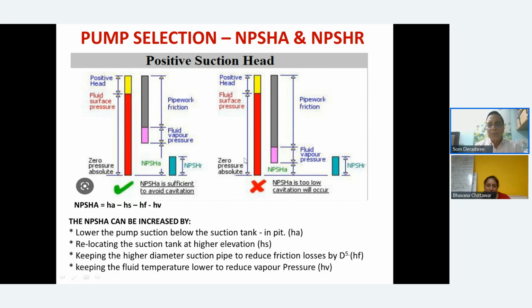So this is okay. But for example, if your pipe friction is much higher, supposing you have a valve or some constriction, or there is a branching on the suction side, the friction has increased. The fluid vapor pressure is the same as this, but the friction head has increased. So your absolute available head from the zero point is only this much, whereas NPSH required was here. So this will definitely have cavitation.